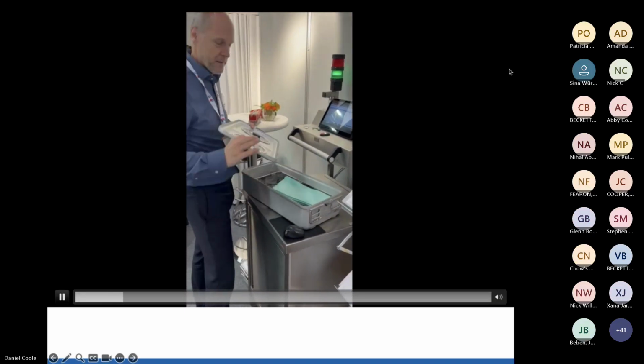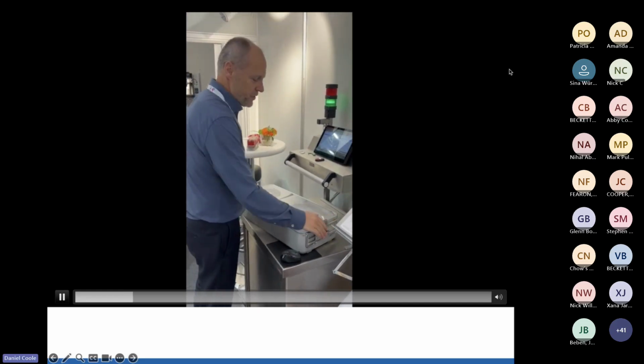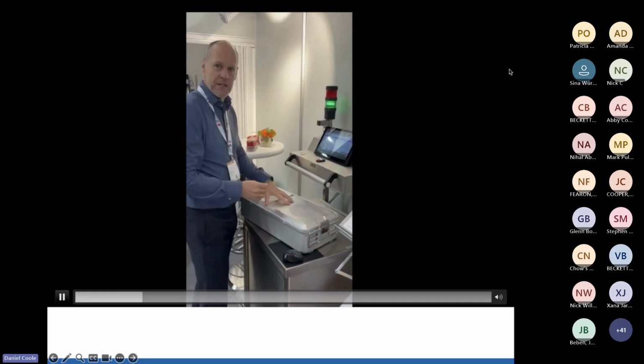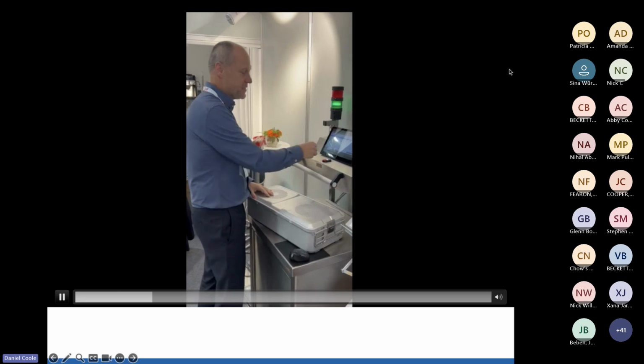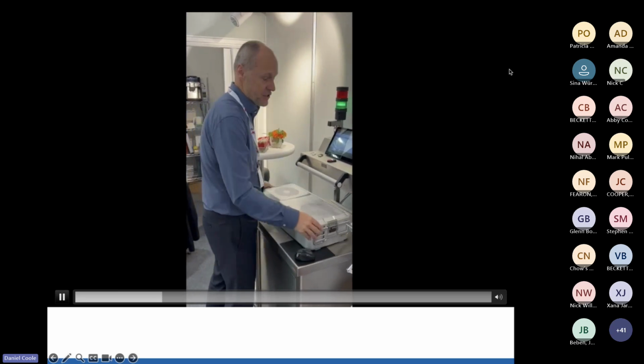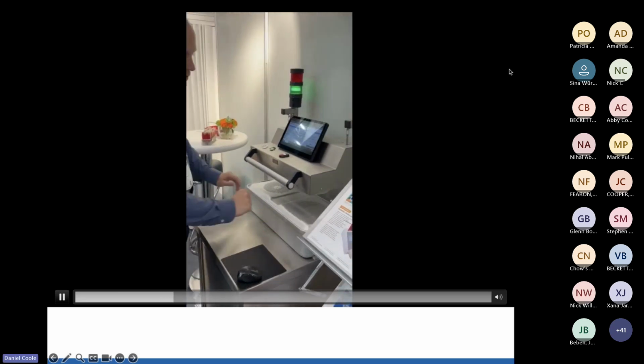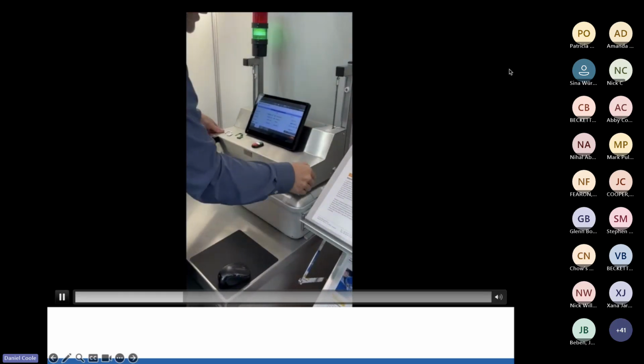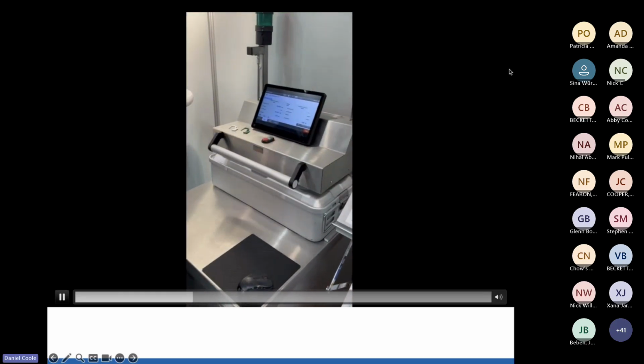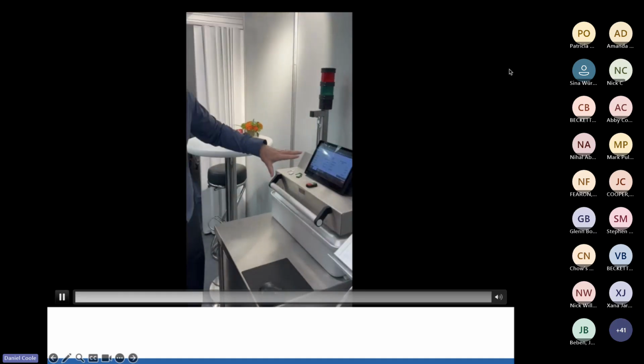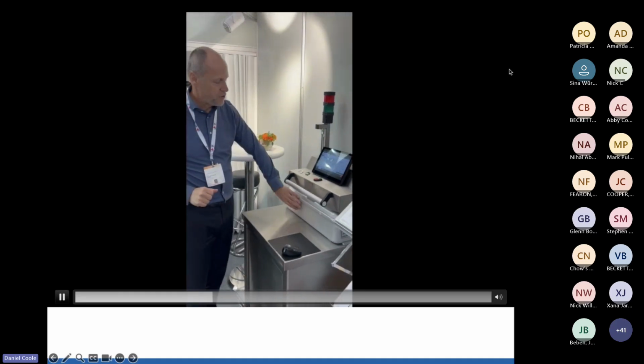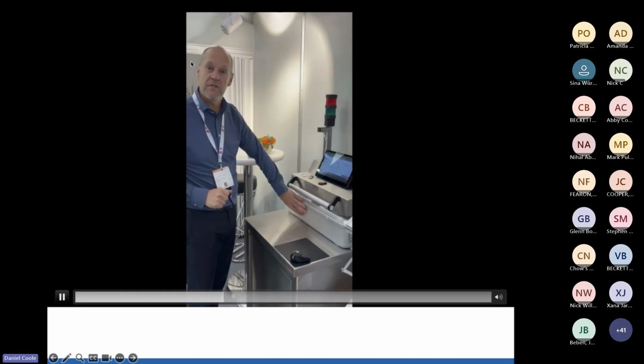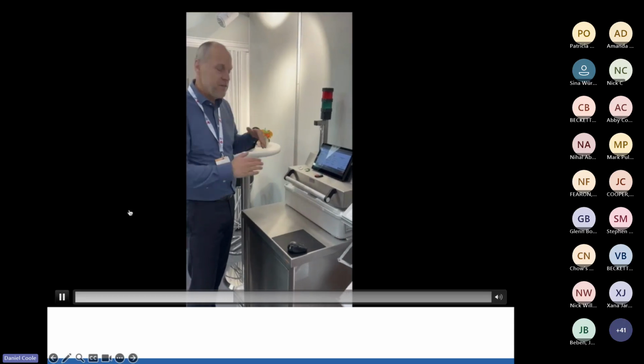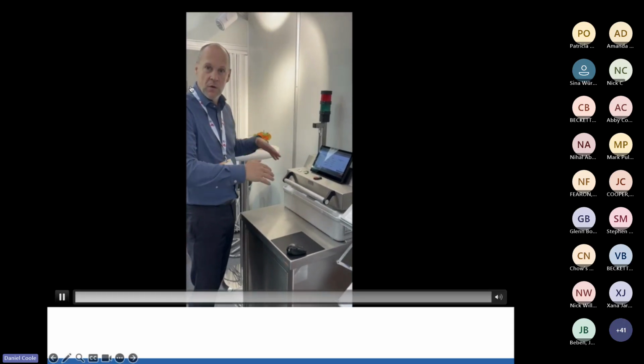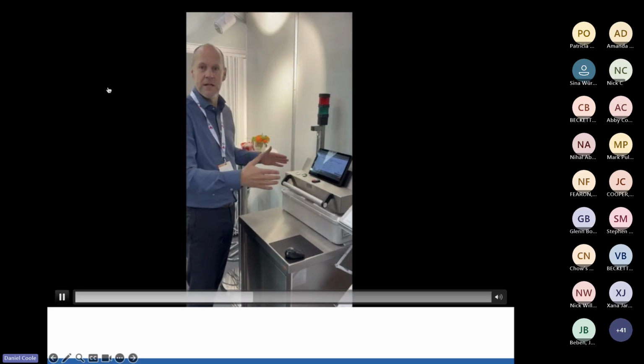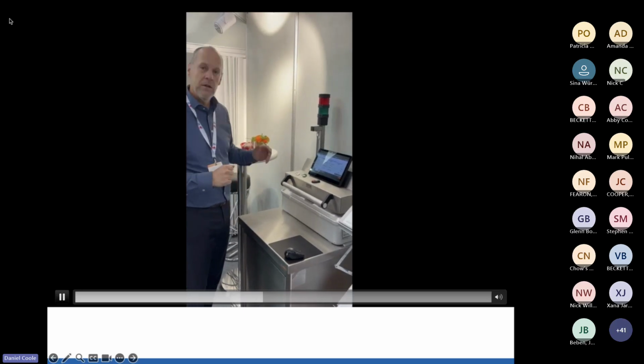That's good. So it's very simple. Before you seal the container, you have packed the instruments in there. Before you seal it and sterilize the instrument, you put the container in the test device, close the lid, press the start button. What we are doing now is we make a small vacuum inside of the container of 25 millibar. When we achieve that pressure, we close all the valves and we stabilize the whole system. Then we start the measurement.